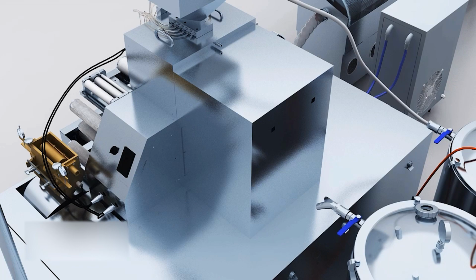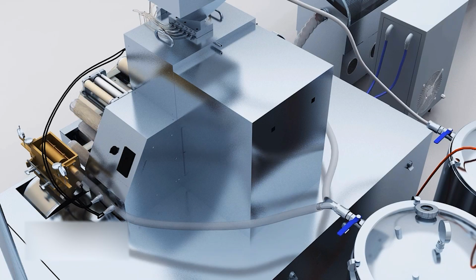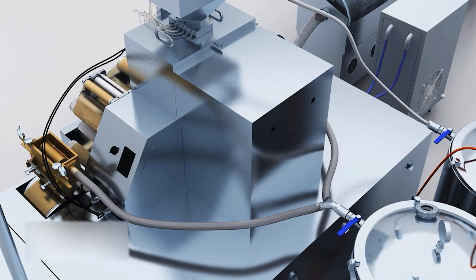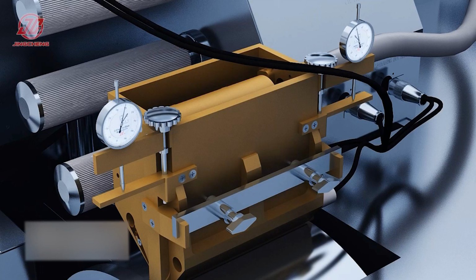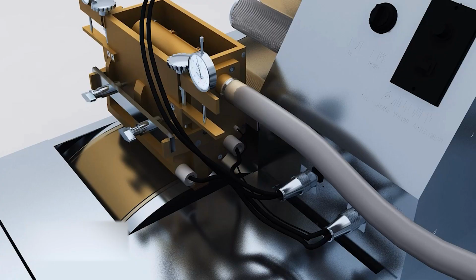Pre-boot preparation. 1. The insulated gelatin storage tanks are all connected with the main machine's gelatin box interface and held with hose clamps, with insulation wrapped outside. Apply rubber pipe for insulation. Adjust the bezel on both sides of main machine's gelatin box for complete contact without gaps onto the rubber surface of the wheel. 2. The 2-side gelatin boxes, syringes, electric rods, and sensor are respectively inserted into their aviation interface plug.